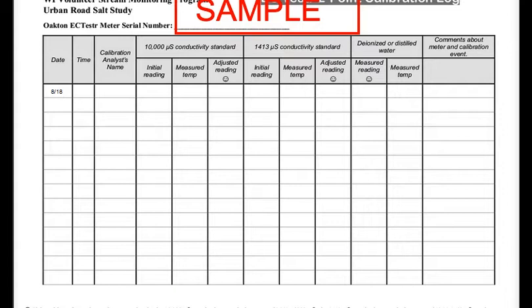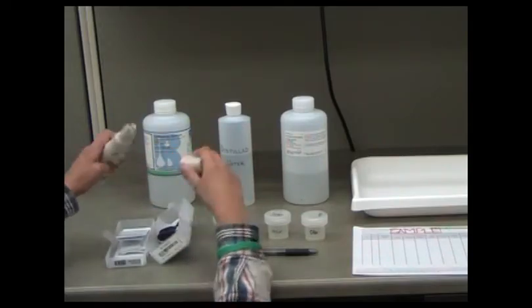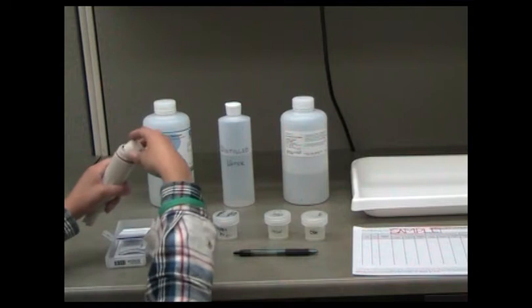Record the date, time, and name of volunteer or individual calibrating the meter on the two-point calibration log. Unscrew the cap from the top of the meter and remove the protective cover from the bottom of the meter. Set these pieces aside.